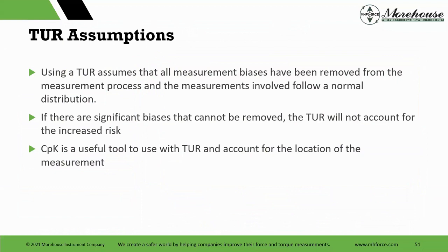So TUR assumptions: using a TUR assumes that all measurement biases have been removed from the measurement process. We're showing you here what the assumption is, and people really don't do this. It also assumes the measurements involved follow a normal distribution. If there are significant biases that cannot be removed, the TUR will not account for the increased risk. So we've got to remove them. And CPK is a useful tool to use with TUR and account for the location of the measurement.